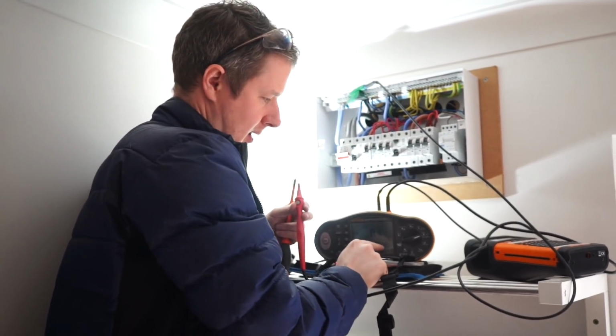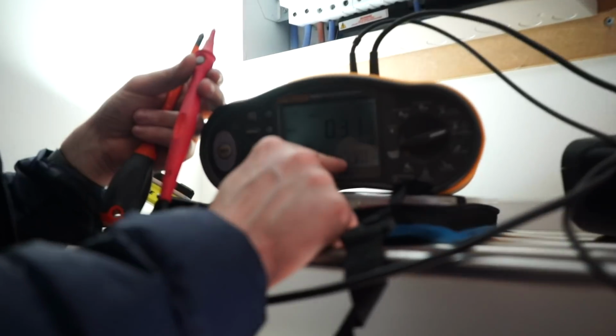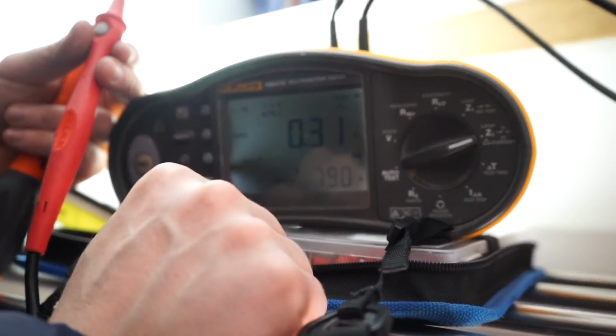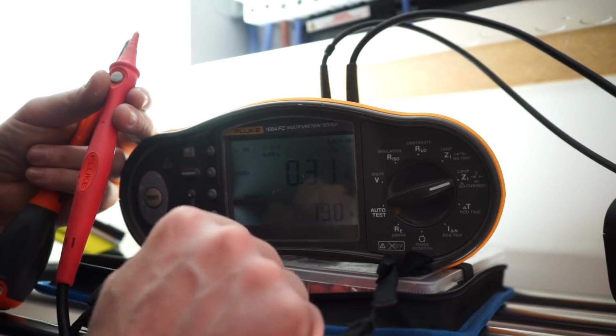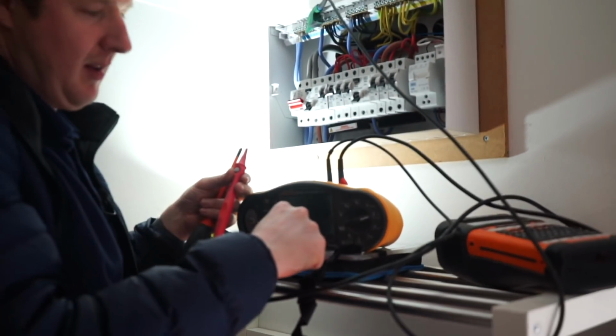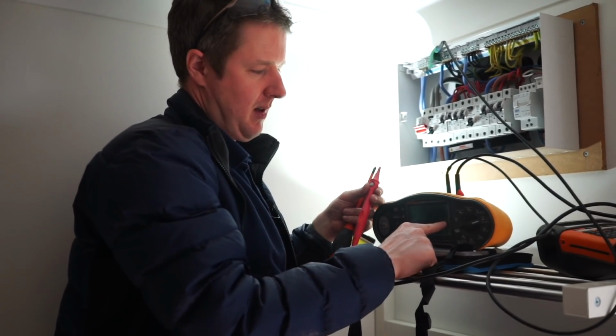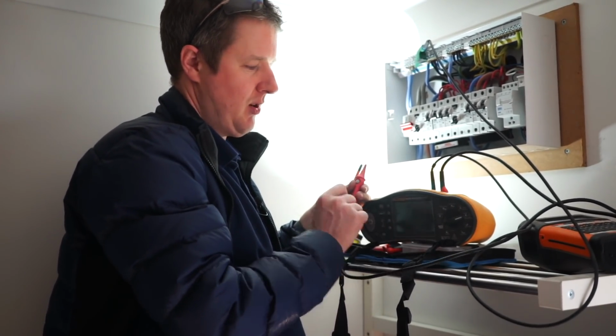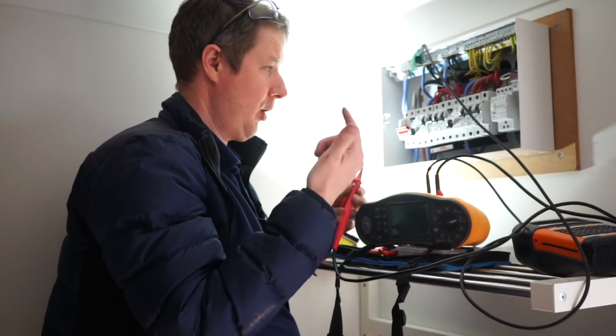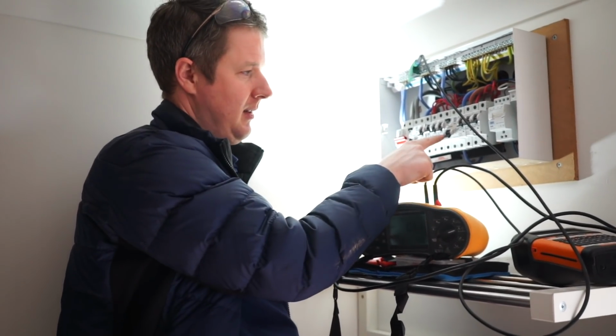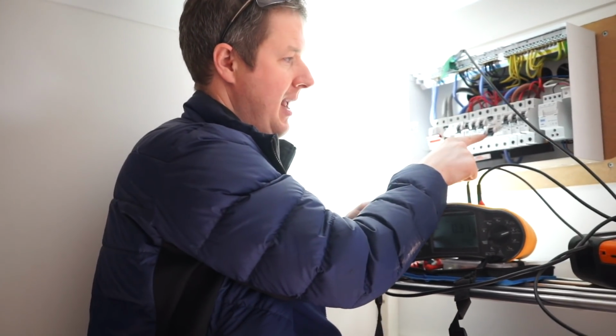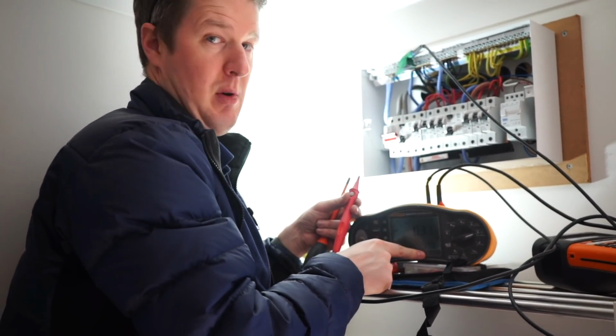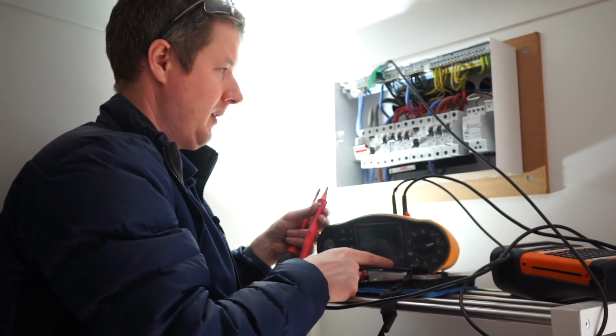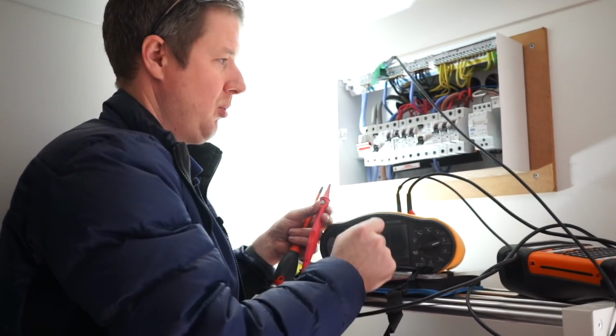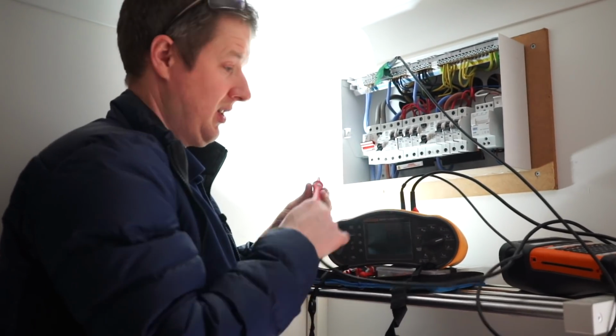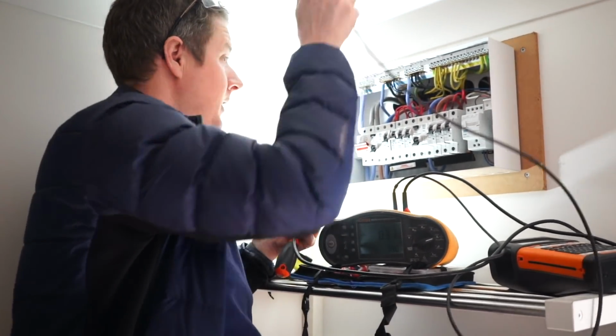So that is our prospective fault current, which is the maximum current that can flow to neutral in this case, in the event of a fault. So imagine if someone cut through the main tails coming into the board, that's the resistance of those main tails, and therefore that means that 790 amps is the maximum amount of current that can flow through. So what we have to check is if the circuit breakers in the consumer unit are rated to be able to withstand that maximum prospective fault current, and these are rated at 6,000 amps, so that's more than capable. Yeah, just a little explanation of why we do that test, really. So we're good to go.